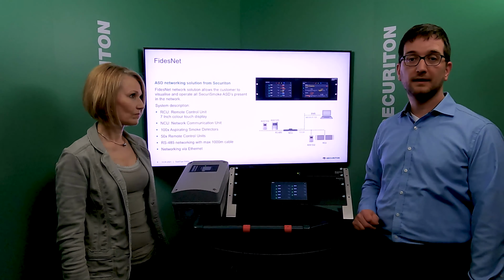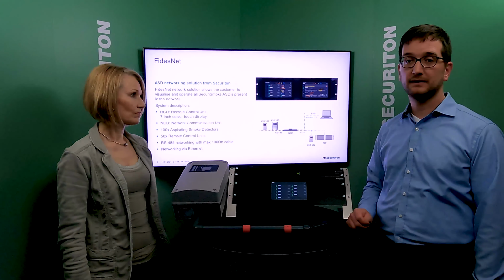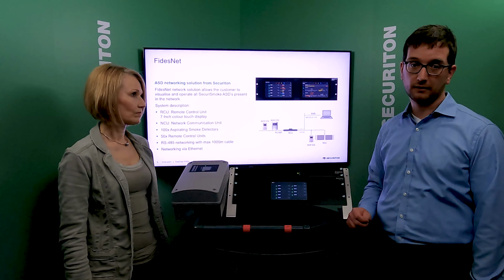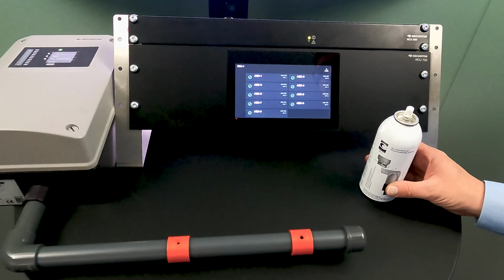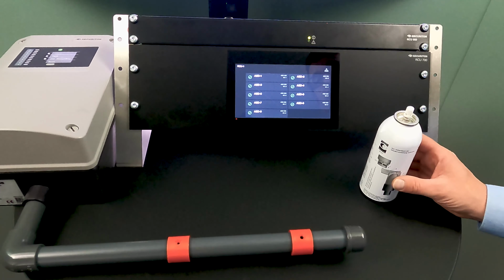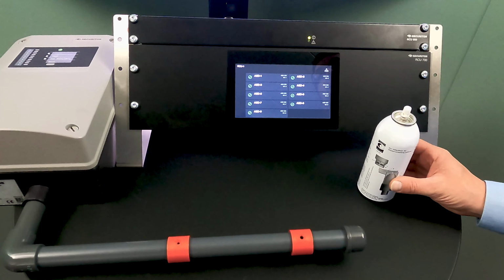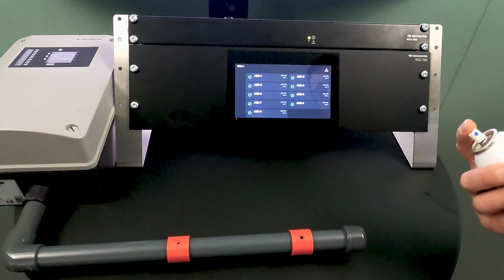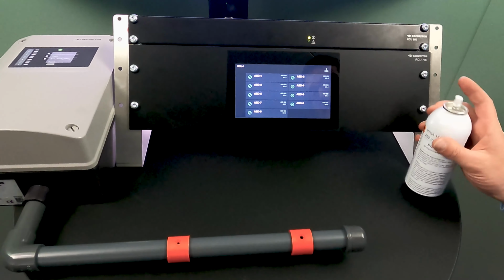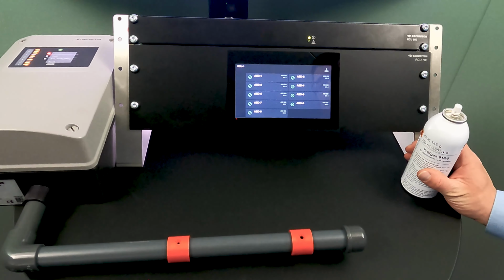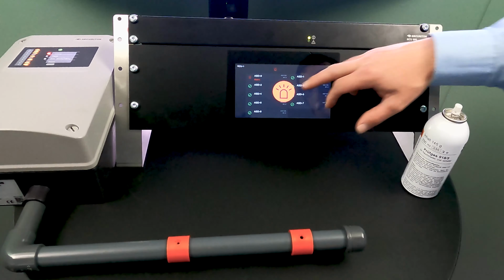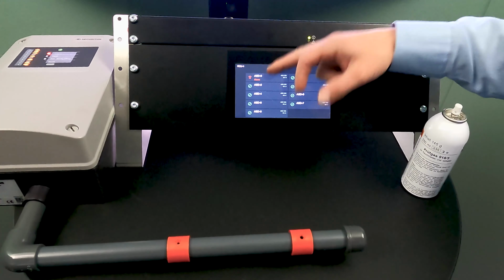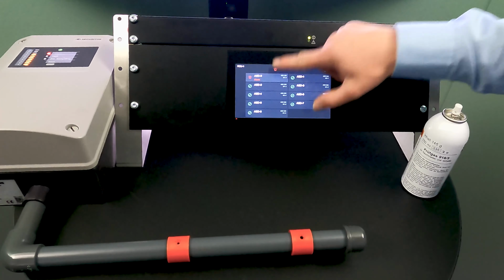We can show you now as a live demonstration how it will look like when we have a fault or an alarm. So the product demonstration, you can see the device list, and all the connected ASDs are shown on this device list. Can be up to 100 ASDs. They are listed by the event urgency. So means I can show it when I put the smoke spray inside of the ASD. You can see ASD number 9 is in alarm, and the prioritization is now on top. So alarm event is a top event.